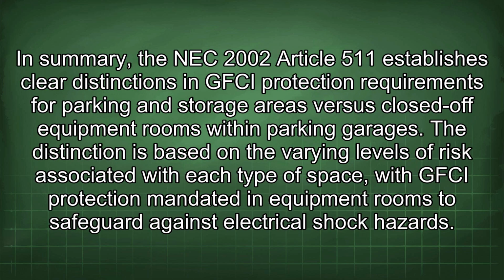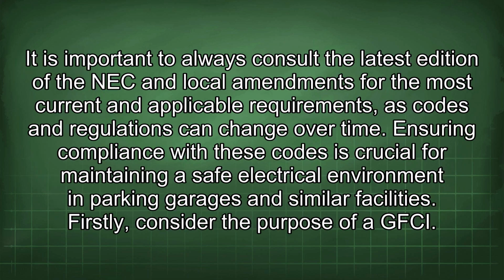In summary, the NEC 2002 Article 511 establishes clear distinctions in GFCI protection requirements for parking and storage areas versus closed-off equipment rooms within parking garages. The distinction is based on the varying levels of risk associated with each type of space, with GFCI protection mandated in equipment rooms to safeguard against electrical shock hazards. It is important to always consult the latest edition of the NEC and local amendments for the most current and applicable requirements, as codes and regulations can change over time. Ensuring compliance with these codes is crucial for maintaining a safe electrical environment in parking garages and similar facilities.